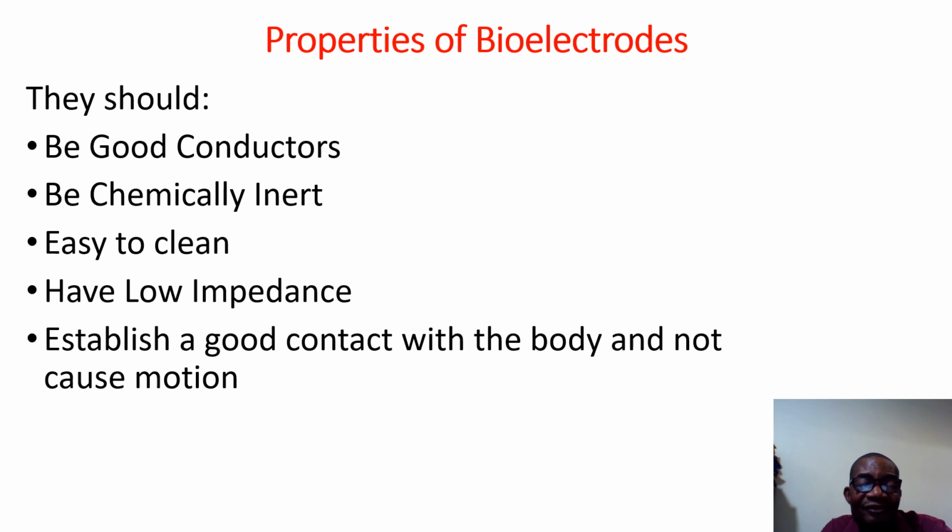They should also have low impedance. Bioelectrodes should have low impedance since they are good conductors of electricity. Bioelectrodes also should establish a good contact with the body and not cause motion, because when there is motion, then motion artifacts are generated, which will affect the quality of results.